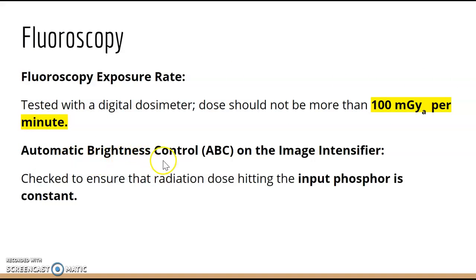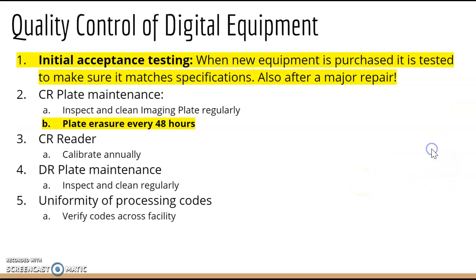The 100 milligray per minute fluoro limit appears on board review frequently — make a flashcard. Automatic Brightness Control, or ABC, is on the image intensifier, and testing ensures the radiation dose hitting the input phosphor remains constant.